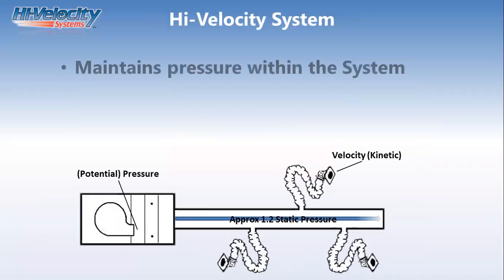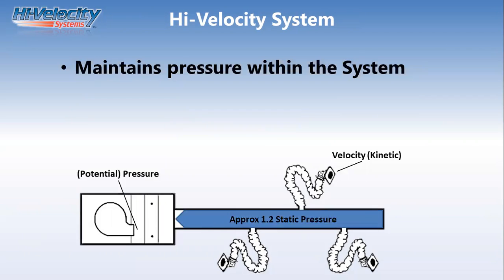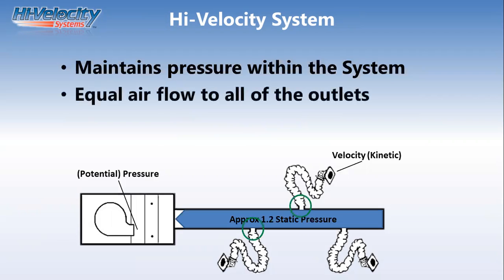With a high velocity system, we operate around 1 inch of static pressure, and we maintain that pressure throughout the entire duct system without duct reductions, without trickling that airflow to the end of the line. When we turn on our fan, it pressurizes at the end cap back to the fan coil with an equal consistent static pressure, which gives us numerous advantages on where we can run ductwork and how long we can run ductwork versus traditional duct systems. With that equal static pressure, it gives us equal airflow to all of the outlets on our high velocity duct system. It's a self-balancing system.